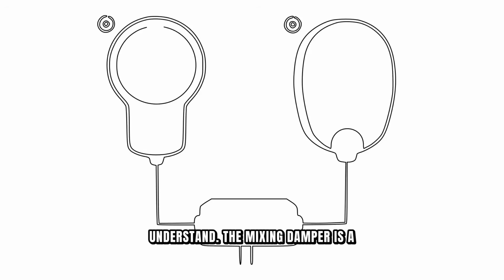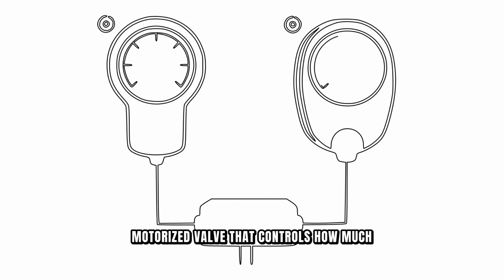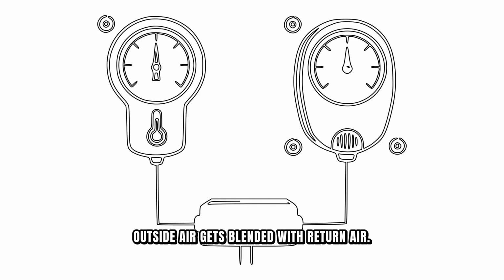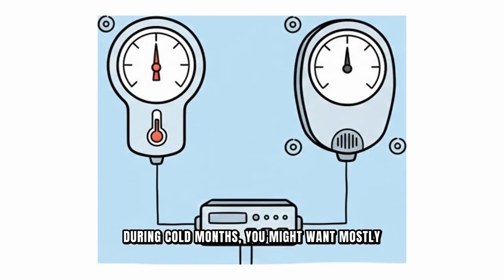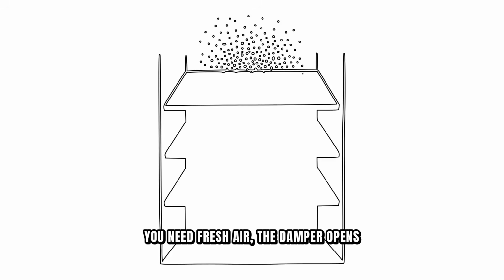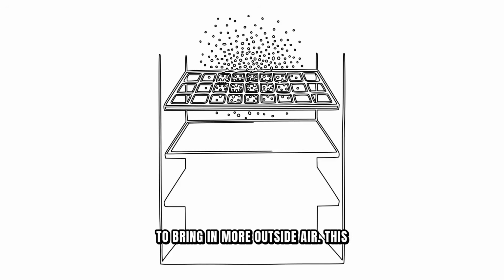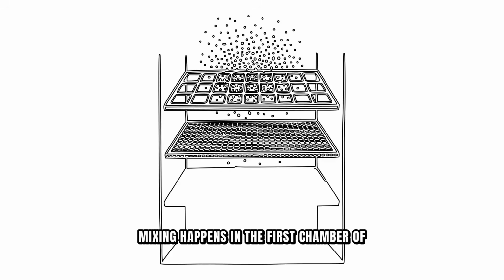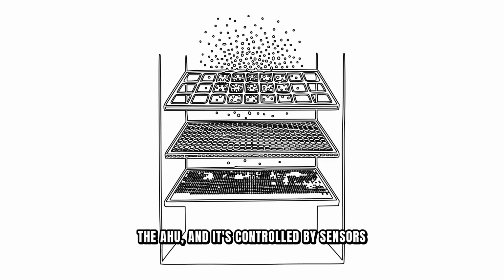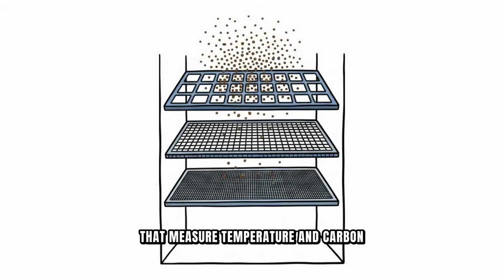The mixing damper is a motorized valve that controls how much outside air gets blended with return air. During cold months, you might want mostly return air because it's already warm from inside the building. During warmer months, or when you need fresh air, the damper opens to bring in more outside air. This mixing happens in the first chamber of the AHU, and it's controlled by sensors that measure temperature and carbon dioxide levels throughout the building.